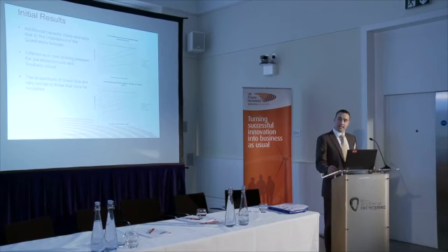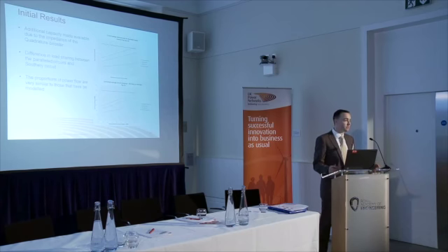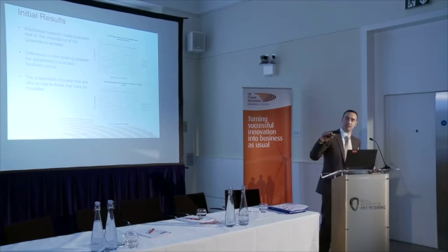What you can see from here, the top graph being the modelled expectations for the impact of the quad booster, and the bottom one based on measurements we've obtained from site. These are averaged measurements, with the solid line being based on the actual data and the dotted line being based on projections from this actual data. Hopefully you can see that the proportion of power flows through the lines are very similar to what we expected.